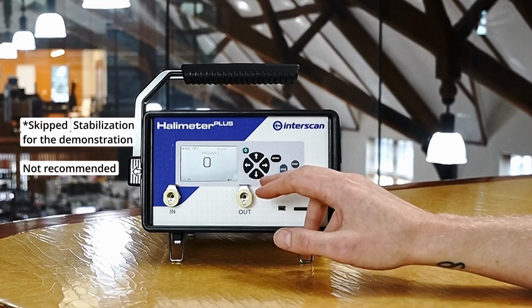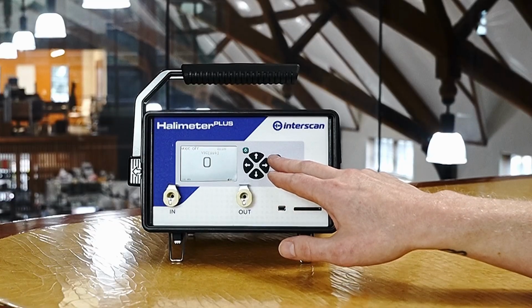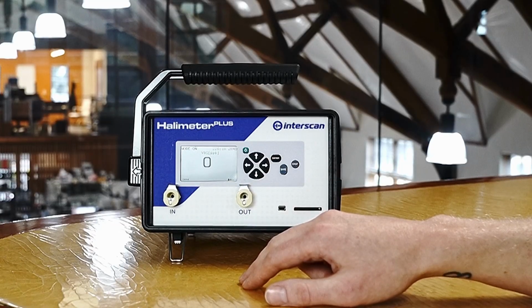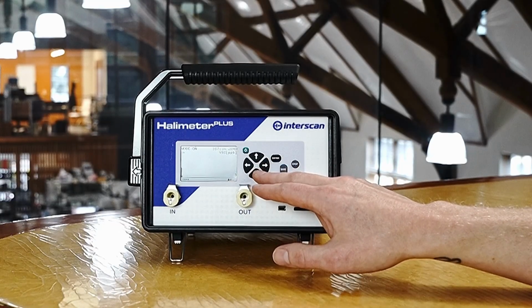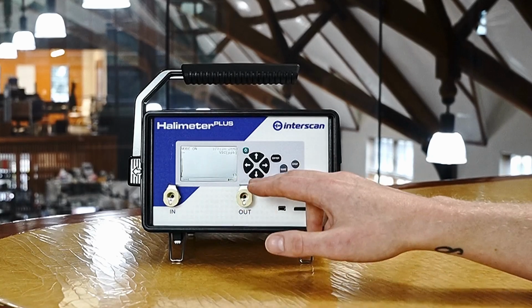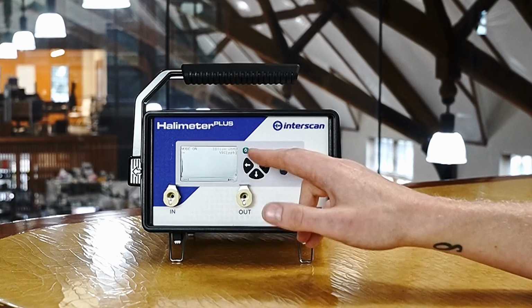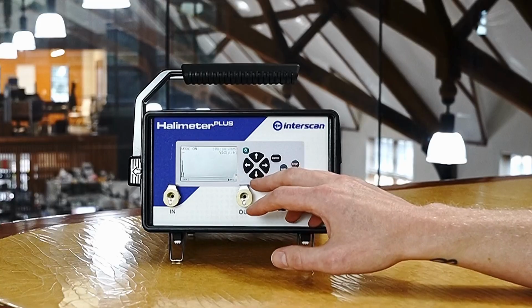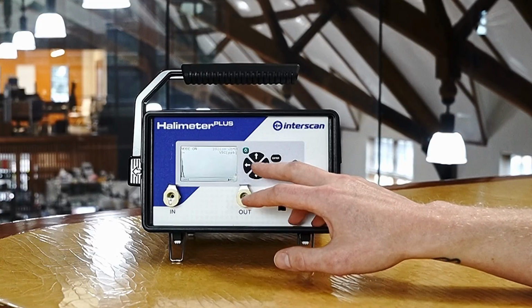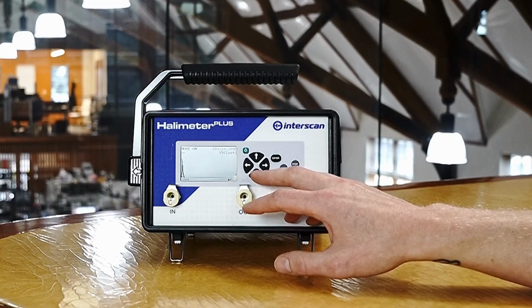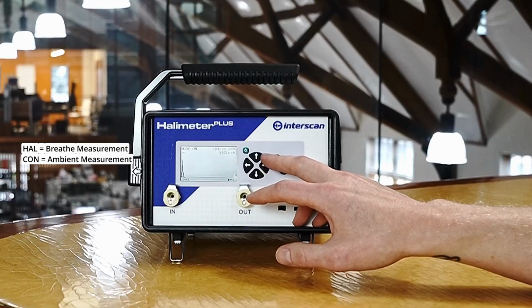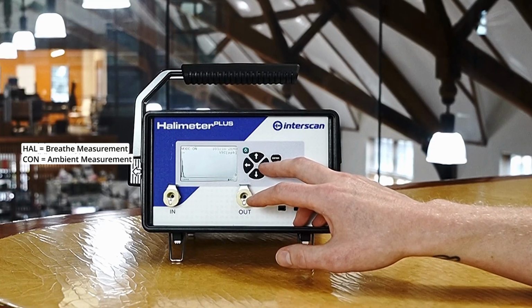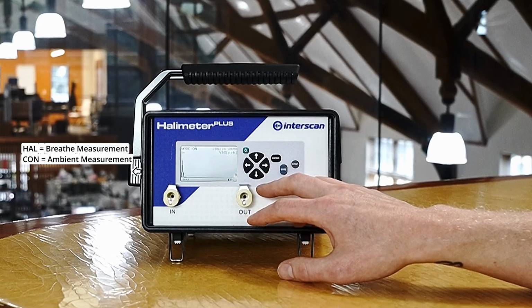Once your sensor has stabilized, you can restart your pump by pressing enter. And if you need to, you can re-zero your sensor from this screen. The major difference of halimeter mode from constant sampling mode is this is designed to detect VSC levels from your breath and not just from ambient measurement in the environment.